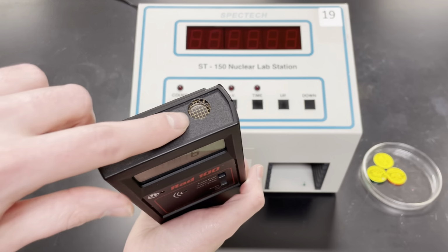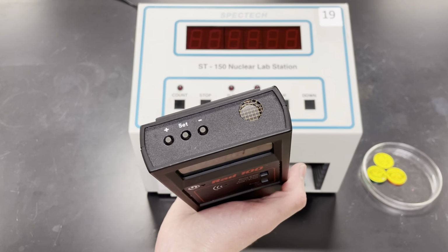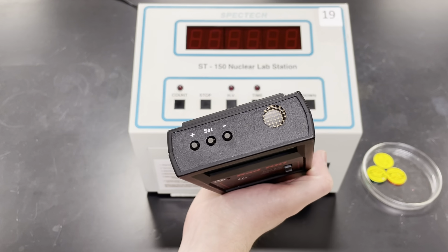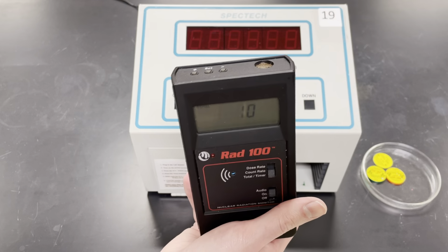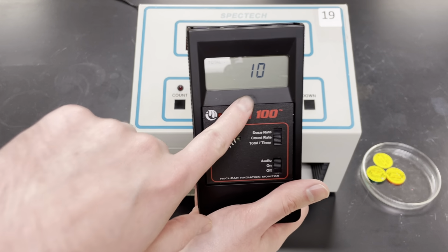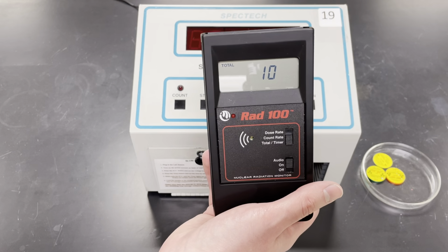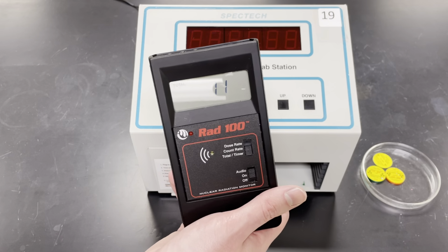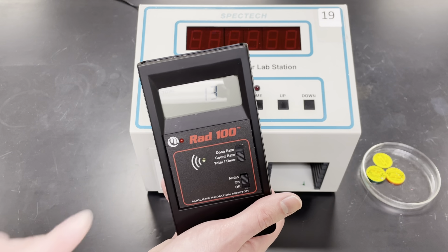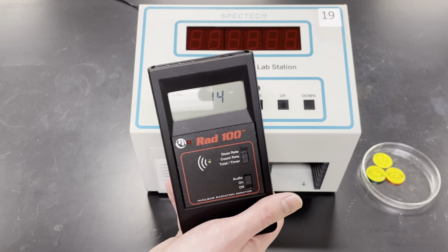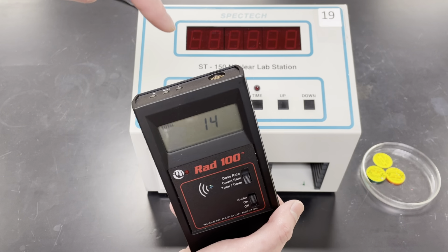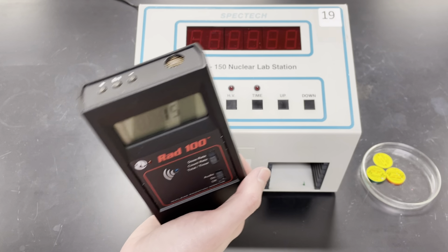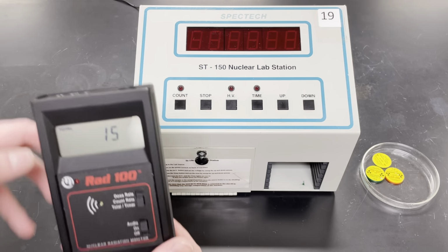So when something passes into this window carrying enough energy to do something with this little tube inside that's full of some low pressure gas, we're able to make an electronic signal that this amplifies and reads out as a number, and gives us a little click to indicate that something has come through. So that could be an alpha particle, a beta particle, or a gamma ray. And just from the counts here, there's not really a way we could tell easily. It's just saying, hey, something flew in here that was strong enough to cause a disturbance in the gas that's inside here.